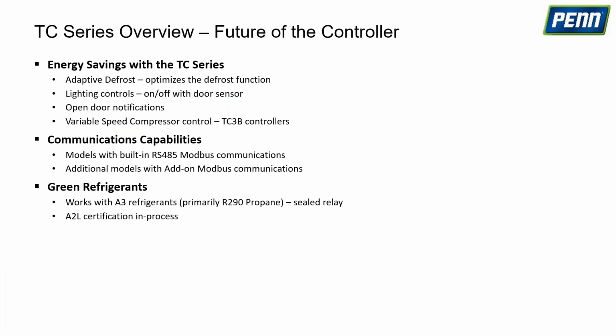Just a quick overview of the TC: as discussed, we have energy savings with adaptive defrost, and with the TC3224 controller, it also has lighting controls that turn on and off with any type of door sensor. We also have open door notifications in case someone leaves the door open too long, which lets heat in, and you'll be notified. There's also energy savings with the variable speed compressor controller.